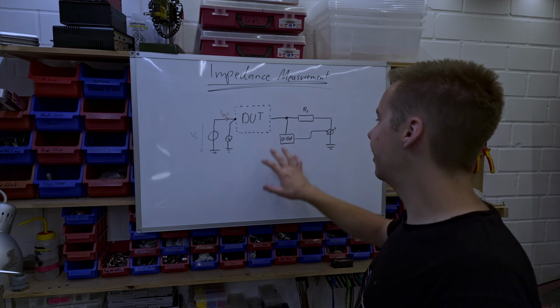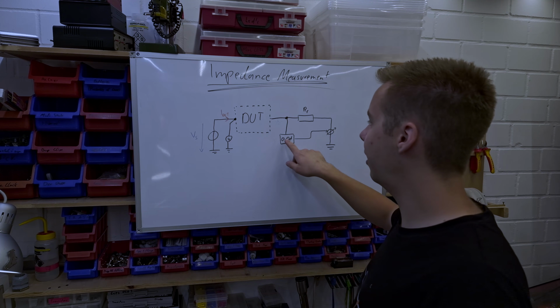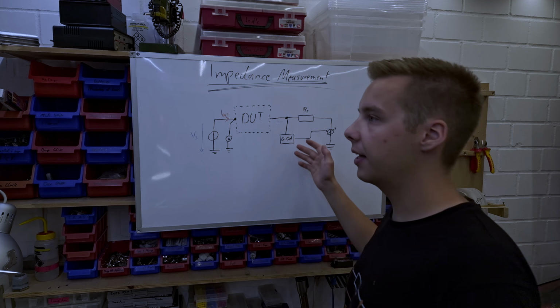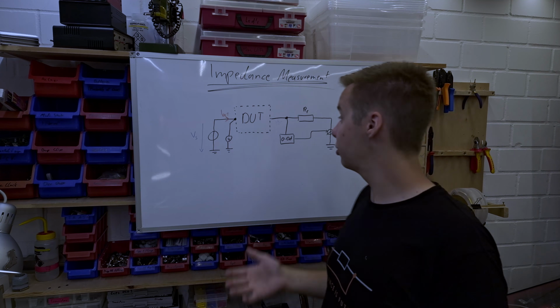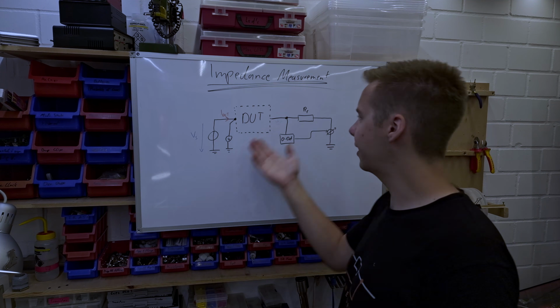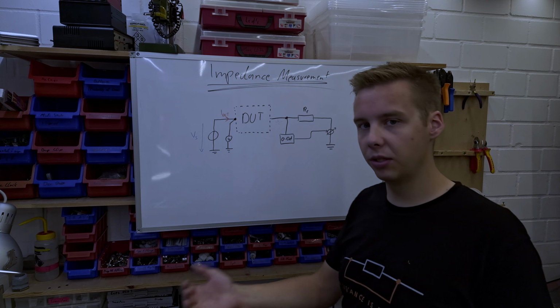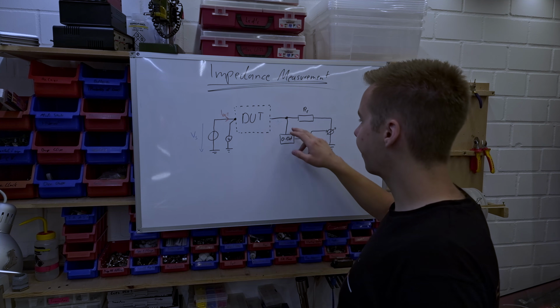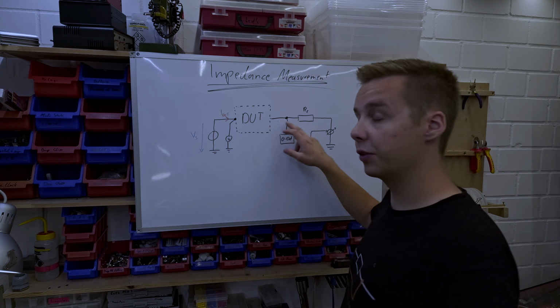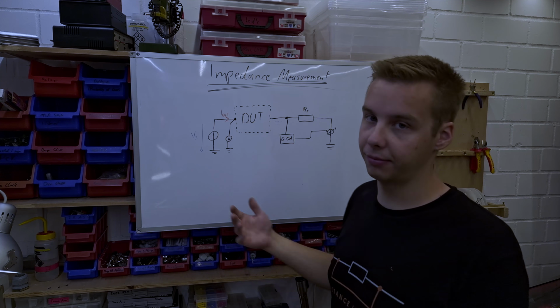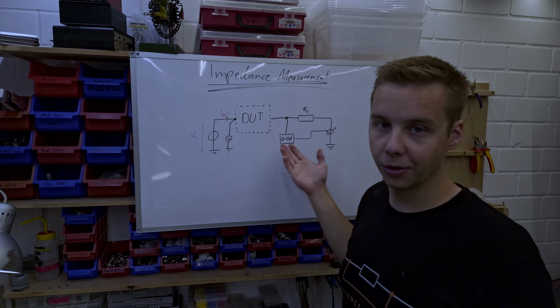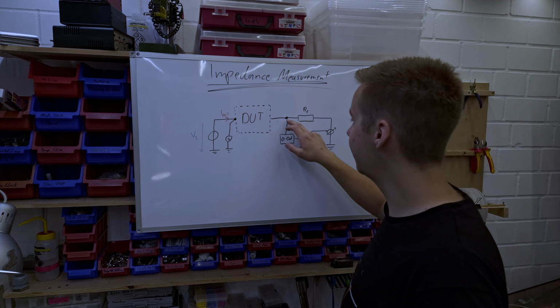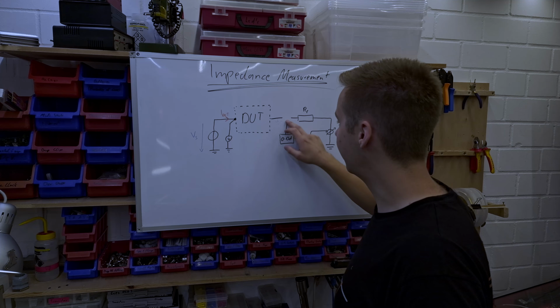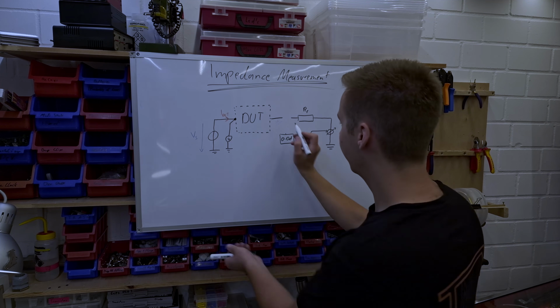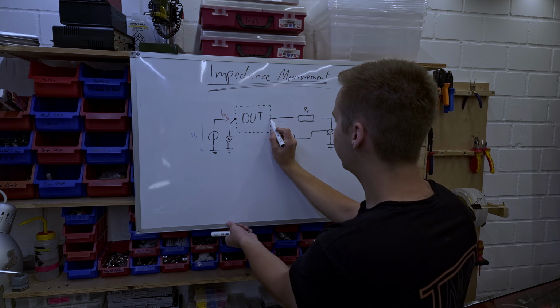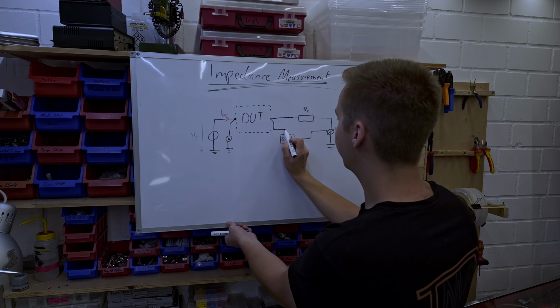And a similar thing happens here because we have a null detector that detects the voltage at this point and tries to reduce it back to 0. We somehow need to compensate for the voltage drop across the cables here as well. And once again, voltage drop across cables we can compensate fairly easily by, instead of connecting that thing here, connecting this directly at the device under test.